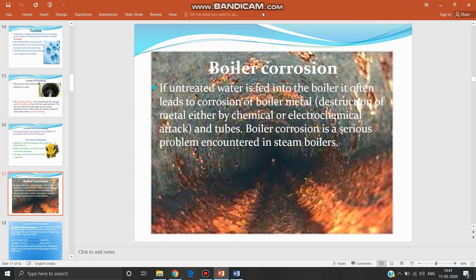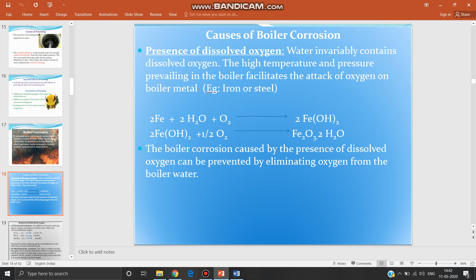What are the reasons for boiler corrosion? The first reason is presence of dissolved oxygen. Water invariably contains dissolved oxygen. The high temperature and pressure prevailing in the boiler facilitates the attack of oxygen on boiler metal. Like whatever we have studied in the electrochemical theory of corrosion, the same process will happen here also. So those reactions we have given here: formation of ferrous hydroxide, and in the presence of dissolved oxygen you will get hydrated ferric oxide, somewhat like yellow rust. The boiler corrosion caused by the presence of dissolved oxygen can be prevented by eliminating oxygen from the boiler water.